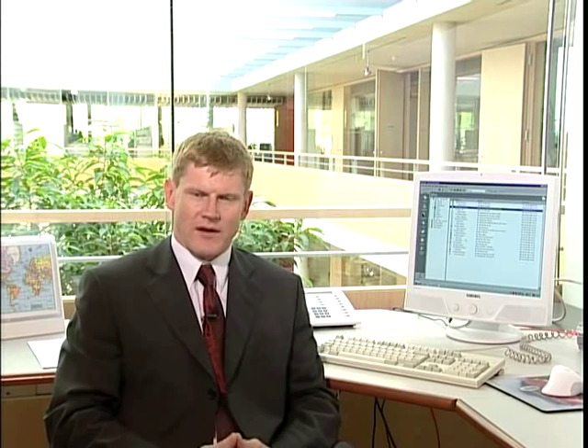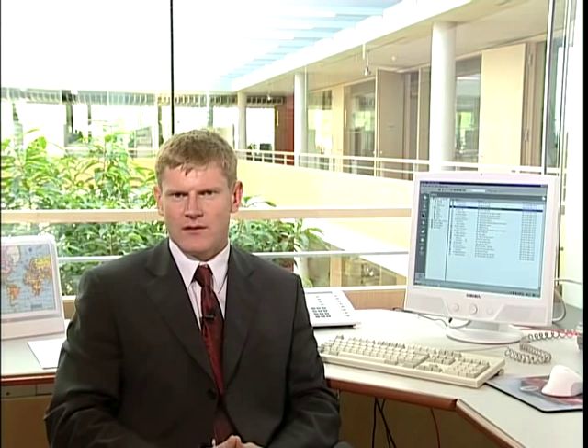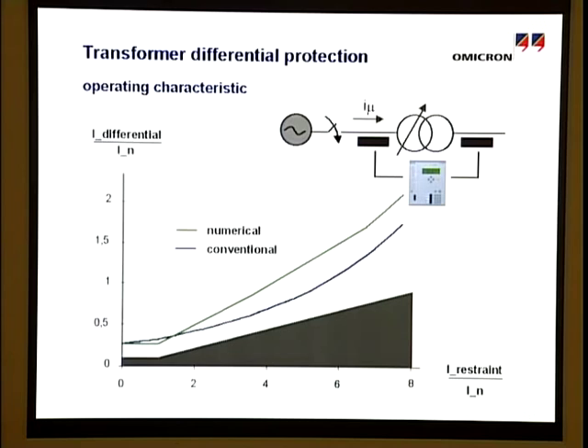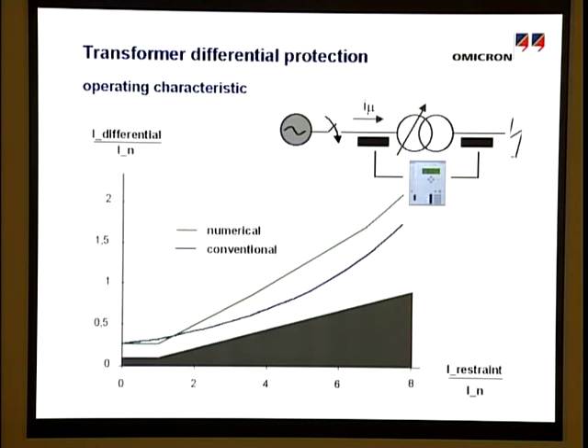Based on an actual event, the following explanation describes the theoretical background and methods for analyzing CT behavior, and explains what has to be considered to set the differential protection system properly. The trip characteristic of a transformer differential protection, defined in the differential restraint area, is mainly determined by differential currents resulting from specific circumstances under normal operation. The magnetizing current and the tap changer are the significant influences within the load area. In case of heavy through faults, the impact of CT saturation is taken into account by increasing the rise of the characteristic.